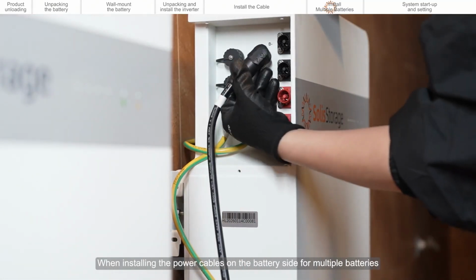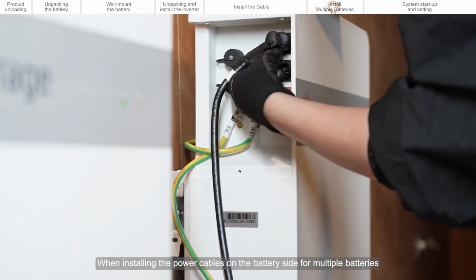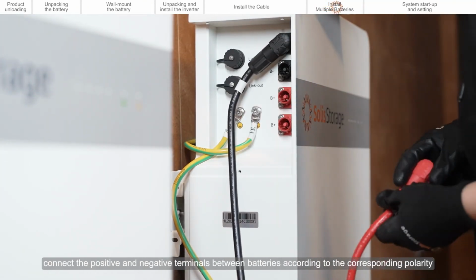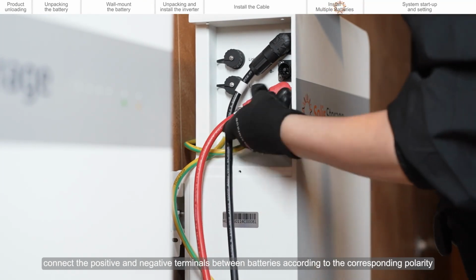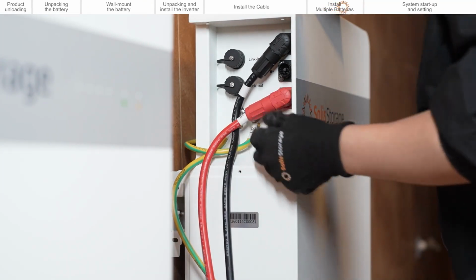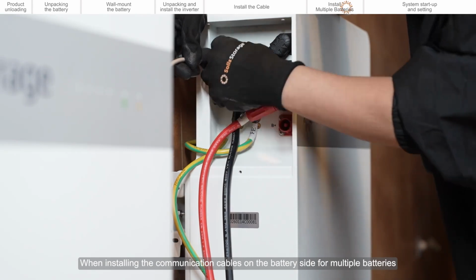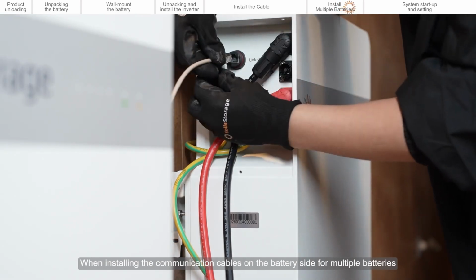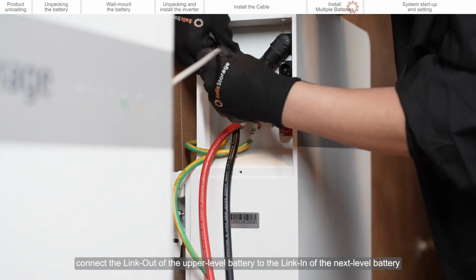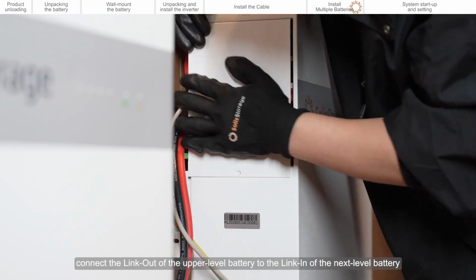When installing the power cables on the battery side for multiple batteries, connect the positive and negative terminals between batteries according to the corresponding polarity. When installing the communication cables on the battery side for multiple batteries, connect the link out of the upper level battery to the link in of the next level battery.